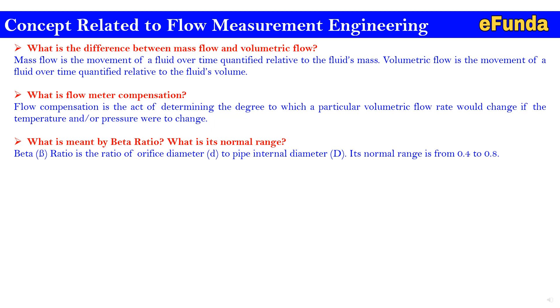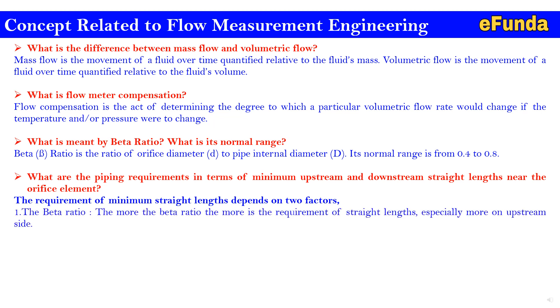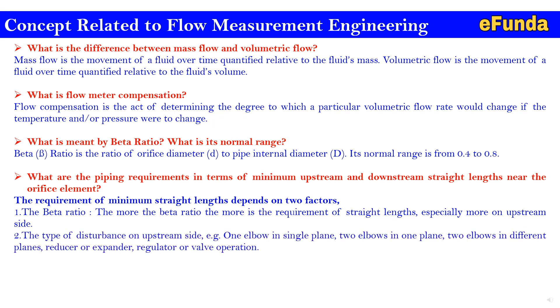What are the piping requirements in terms of minimum upstream and downstream straight lengths near the orifice element? The requirement depends on mainly two factors: first, the beta ratio — the higher the beta ratio, the greater the requirement for straight length, especially on the upstream side. Second, the type of disturbances on the upstream side, such as one elbow in a single plane, two elbows in one plane, two elbows in different planes, a reducer, expander, regulator, or valve operation.